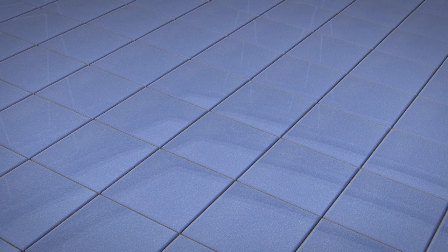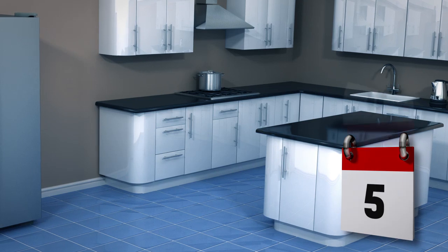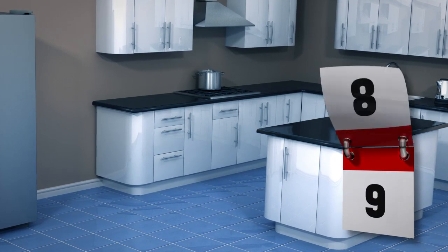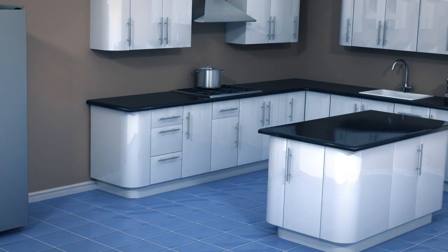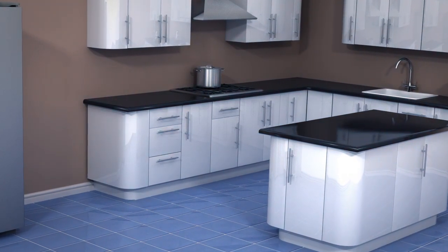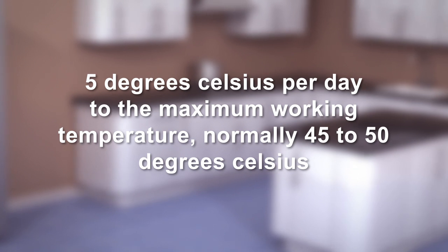Grout the tiles using Ultra Tile Flex Joint Grout. Allow to fully cure before trafficking. The underfloor heating system should not be brought into service for at least 14 days. After this time, the water temperature should be brought up gradually by 5 degrees Celsius per day to the maximum working temperature, normally 45 to 50 degrees Celsius internal pipe temperature.